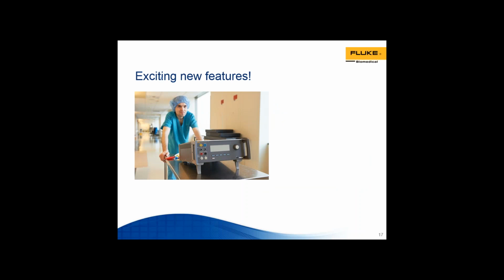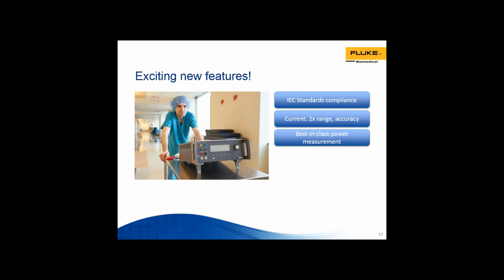So there are some exciting new features that have been added to the QAES3. First of all, the QAES2 had partial IEC standards compliance. So with the QAES3, we're glad to announce that it not only complies with ANSI/AAMI standards, but all the IEC standards for testing electrosurgical devices. We have doubled the range and made the product twice as accurate as its predecessor. So the QAES3 features industry-leading specifications in terms of range and accuracy. It has a best-in-class power measurement spec.